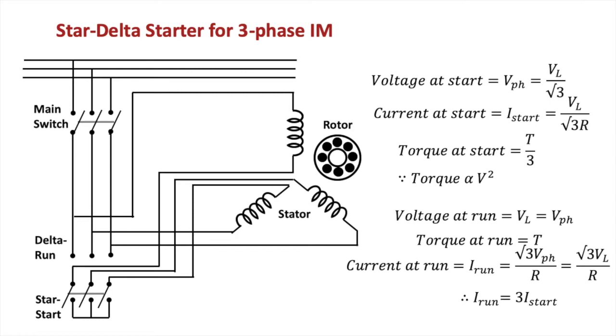Instead of a manual changing over from star to delta, we can also have the automatic connection, because we know that the motor takes almost 2 seconds or 1 minute to run, depending on the inertia of the given motor. You know the mechanical inertia of the given motor. So as per that, you can provide a delay in the given starter, and the motor can be shifted from star to delta under the timer condition, and that can be made as an automatic conversion from star to delta, and the motor will be producing its normal torque. So this is the most common starter used in the industry.